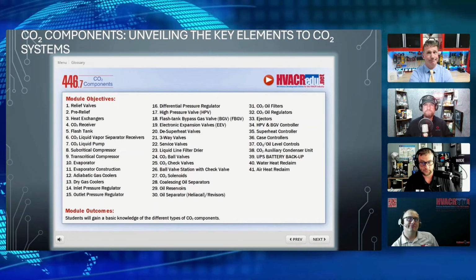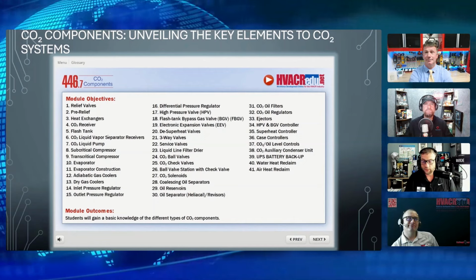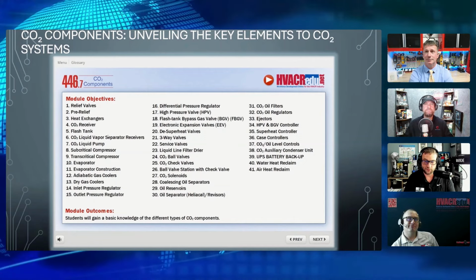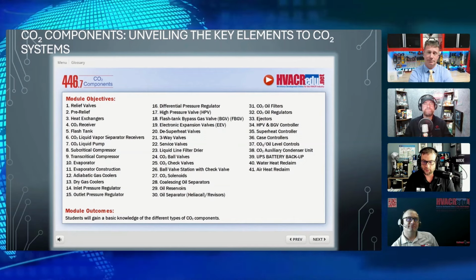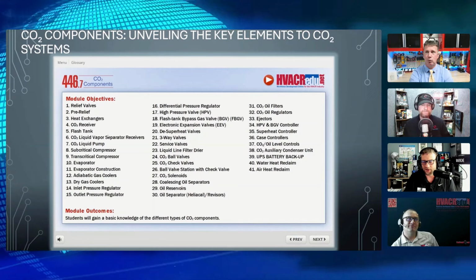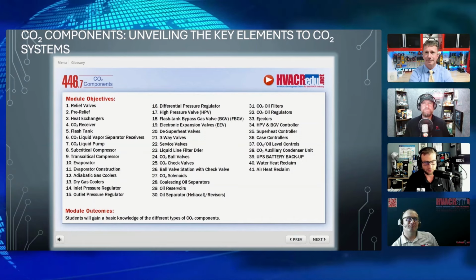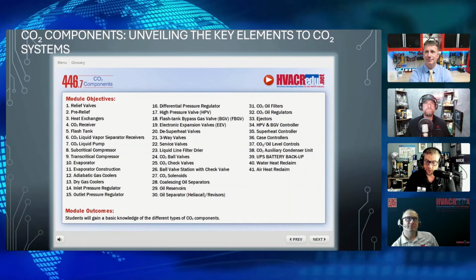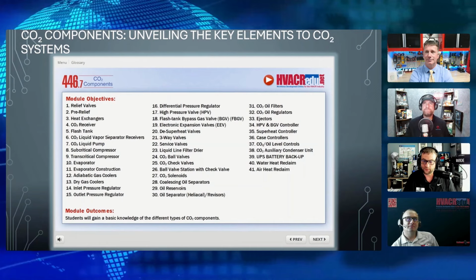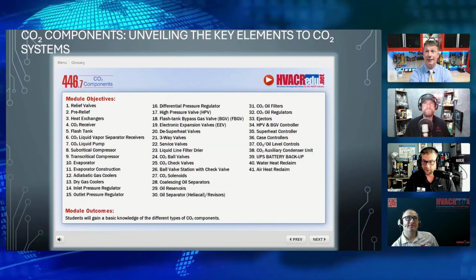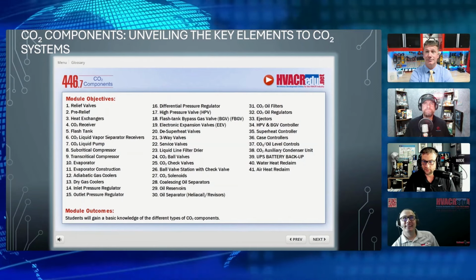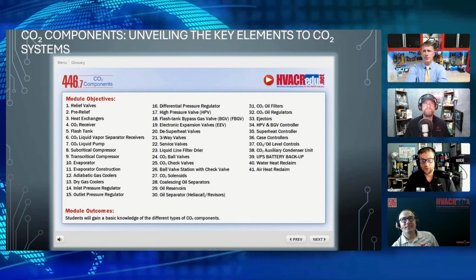Okay. So if you have R22 running low temp, you're running at 6, 10 PSI, right? You hit it with 87 degree water, it might go up to 100 pounds. Okay. With CO2, we have 200 PSI in there. We hit it with 87 degree water. Now we've got 1,055 pounds. Yeah. Kaboom. Wow. The service procedure then is absolutely so different.